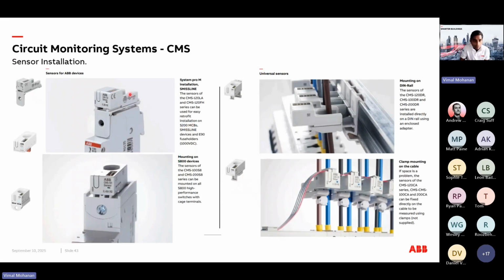The sensors, we have built sensors that fit our breakers nice and clean like this. But our biggest USP is to provide you this open core cable tie version. That means you do not have to disconnect the cable. You can feed the cable right through the sensor itself. The breakers at the bottom now can be anyone's, any third-party breakers, it really doesn't matter. So this is one of our USPs on how easily we can retrofit it.